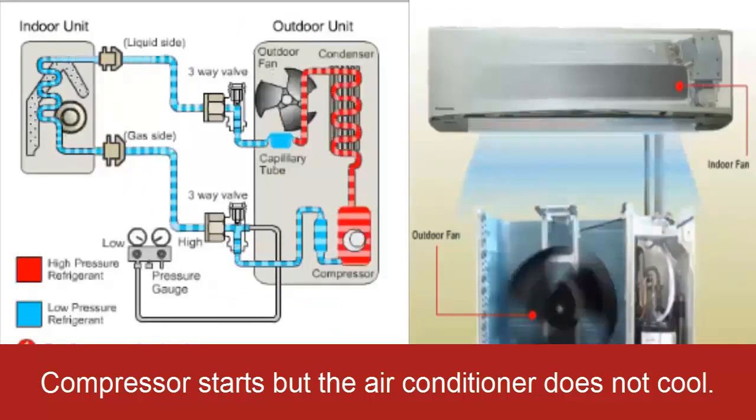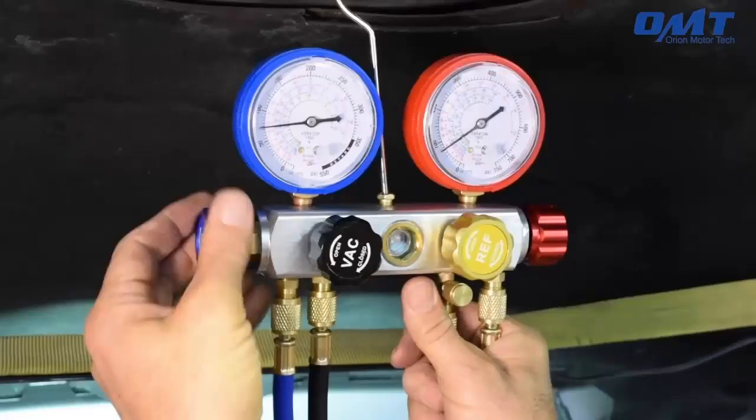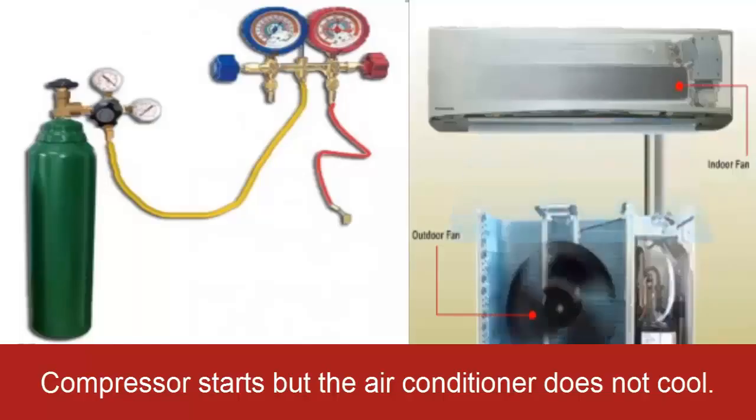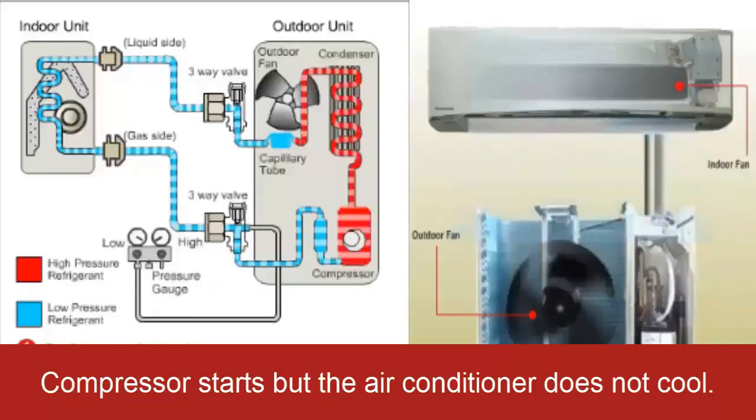4. Condensation problems. The lack of condensation of the refrigerant at the outlet of the external coil can be due to a deteriorated, clogged, or dirty coil. This can cause excessive high pressure and poor equipment performance. It is necessary to clean the external condenser coil or perform internal cleaning, as the case may be. When condensation is faulty, the compressor's electrical consumption is usually higher than normal.